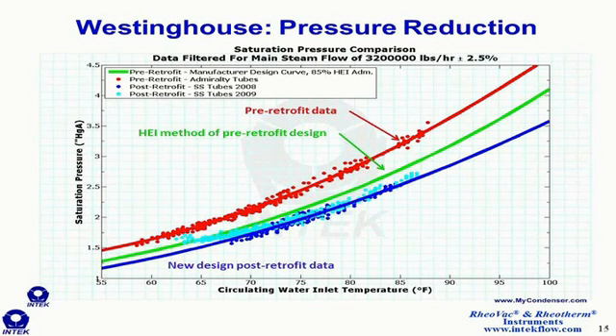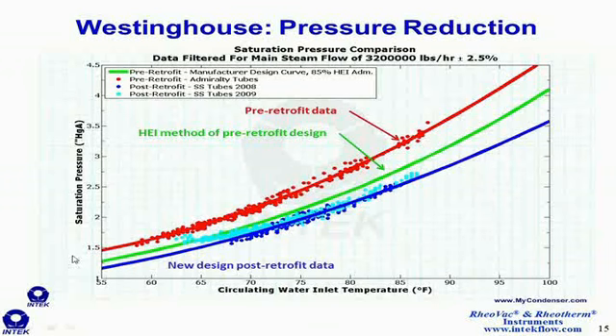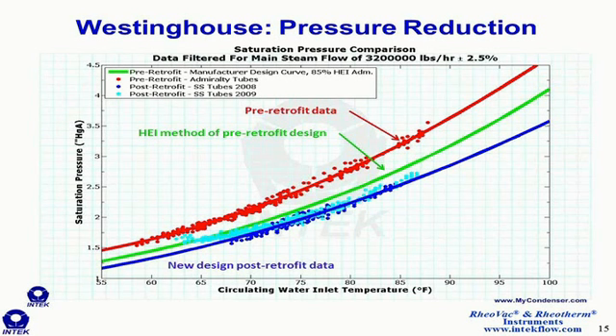And this is the data before and after the retrofit. This plot shows the condenser pressure on the y-axis, the cooling water inlet temperature on the x-axis. The red data is the data from before the retrofit. Prior to the retrofit, the condenser had Admiralty tubes. In an effort to reduce the copper content in their effluent, they wanted to retube the condenser with stainless steel tubes. Now, just moving from Admiralty tubes to stainless steel tubes should have reduced the performance or increased the condenser pressure because stainless steel tubes have a lower heat transfer coefficient than the Admiralty tubes. So one of the motivations for pursuing this condenser retrofit project was to offset that performance loss by going to a lower heat transfer material.